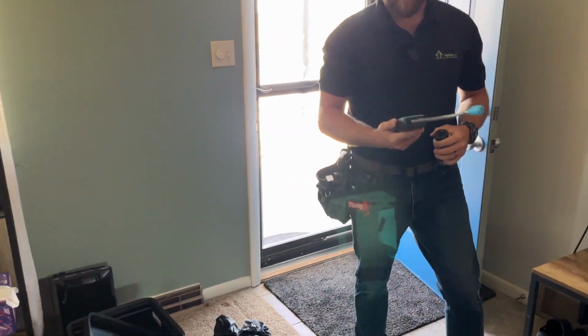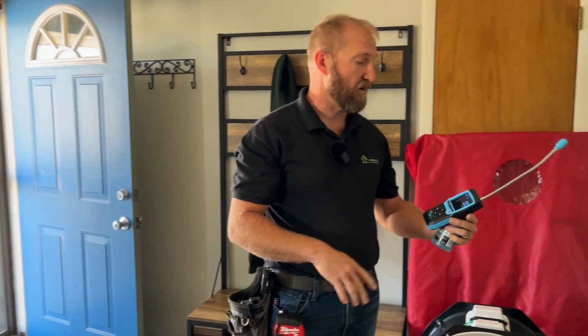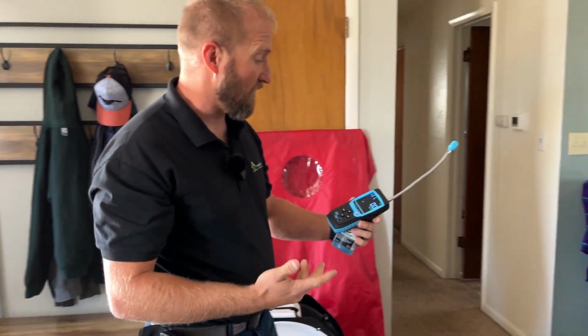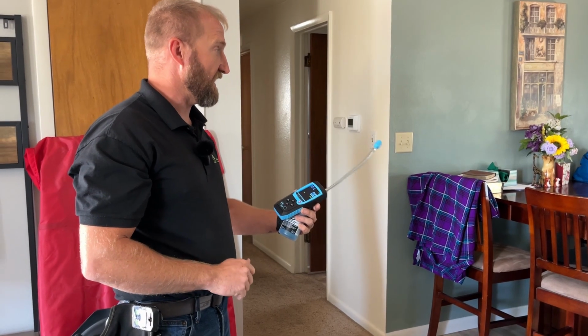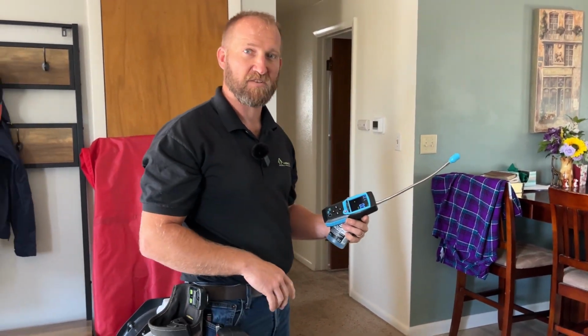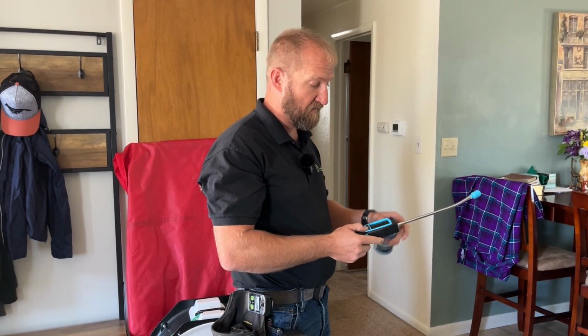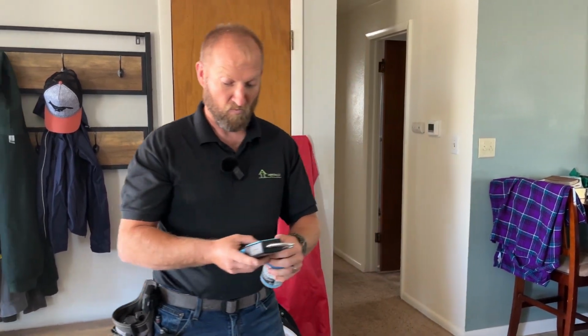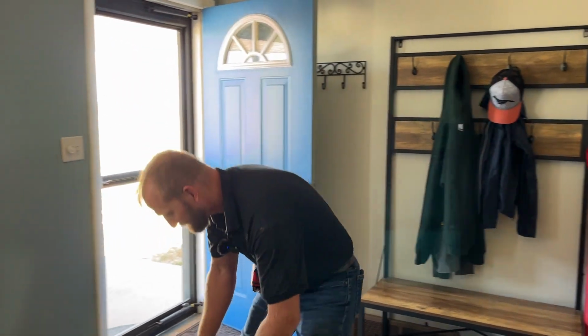So we're going to go ahead and check the levels on one floor of the house here for our test purposes, and we're at 0, so we're doing good inside the house. There's no combustible gas noted in here. So we're going to turn this off for now, and we're going to use this when we check the combustion appliances down in the basement later.